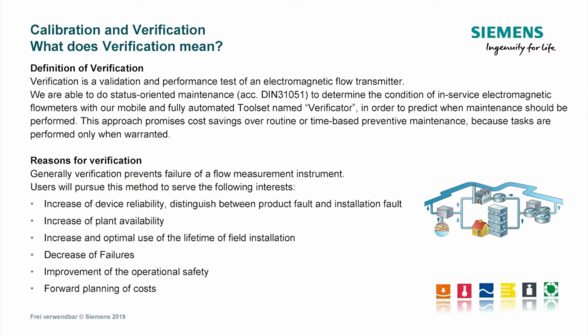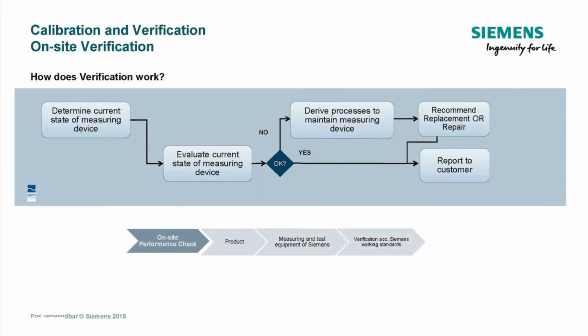Reasons for verification. Generally, verification prevents failure of a flow measurement instrument. Users will pursue this method to serve the following interests: increase of device reliability, distinguish between product fault and installation fault; increase of plant availability; increase and optimal use of the lifetime of field installation; decrease of failures; improvement of the operational safety; forward planning of costs. Here is a flow diagram of Siemens on-site verification process.